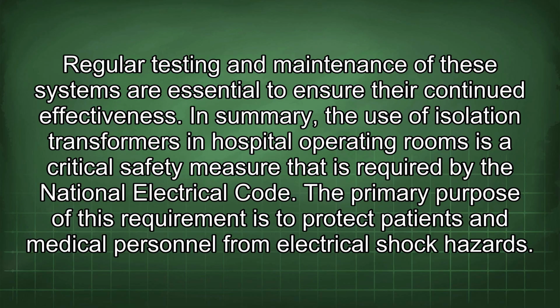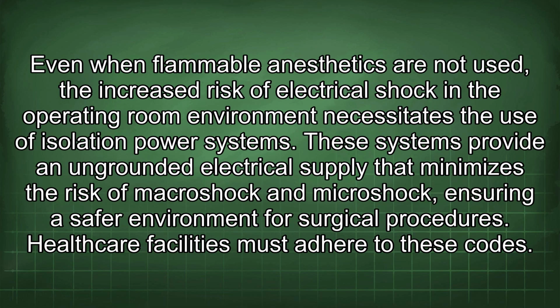In summary, the use of isolation transformers in hospital operating rooms is a critical safety measure that is required by the National Electrical Code. The primary purpose of this requirement is to protect patients and medical personnel from electrical shock hazards. Even when flammable anesthetics are not used, the increased risk of electrical shock in the operating room environment necessitates the use of isolation power systems. These systems provide an ungrounded electrical supply that minimizes the risk of macroshock and microshock, ensuring a safer environment for surgical procedures. Healthcare facilities must adhere to these codes.